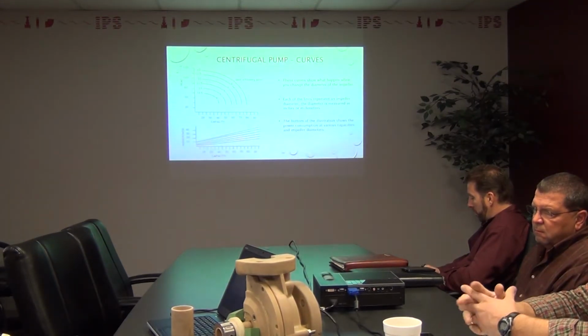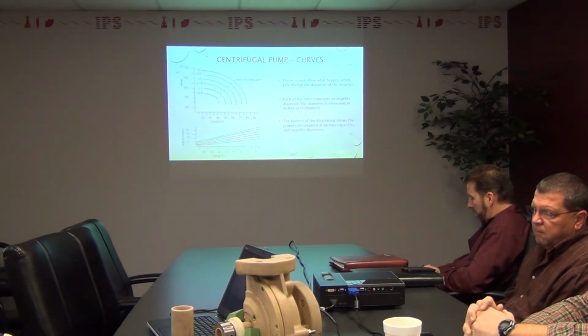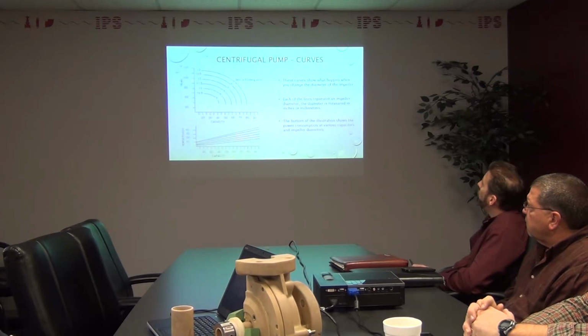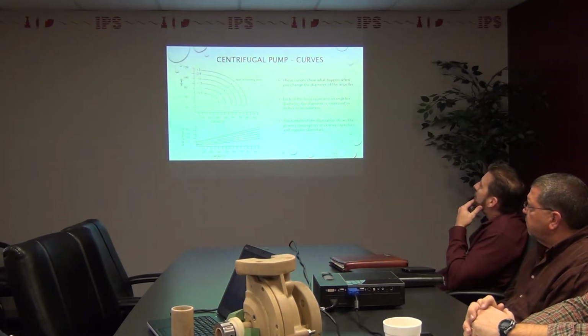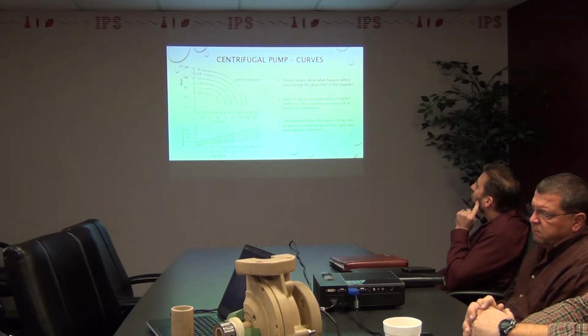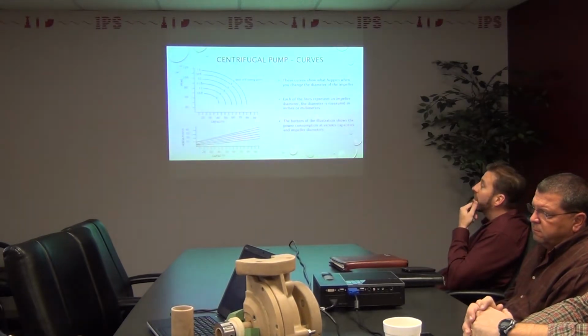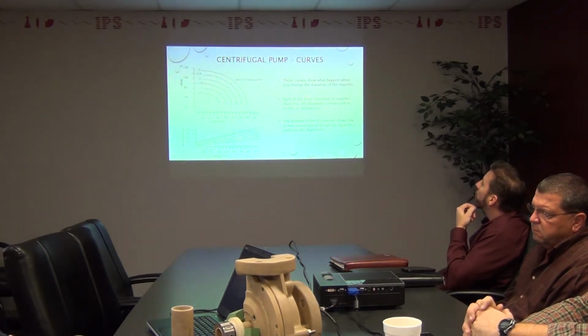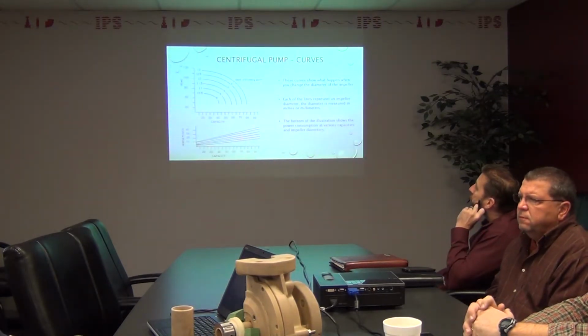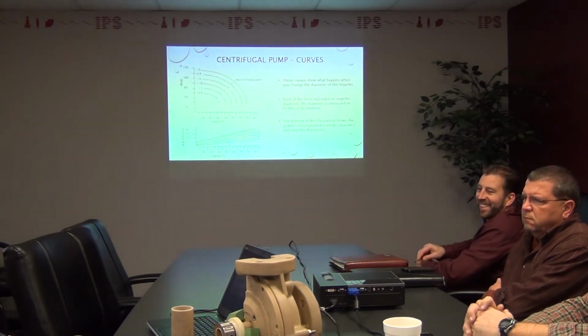So what happens on a pump curve? Customer tells you he's got 100 gallons per minute at 30 feet of head. Turns out he doesn't; he has 30 gallons a minute at 100 feet of head. Turns out he only has 40 feet of head. What happens when they put that pump in? You sized it for 100 feet of head at 30 gallons per minute. They go to throw that in there. What happens to the motor? Yeah. What happens to the whole application? And what you're talking about is a typical example that happens, and one that I always, I don't know who you're going to show this to, but a lot of the engineers miss.